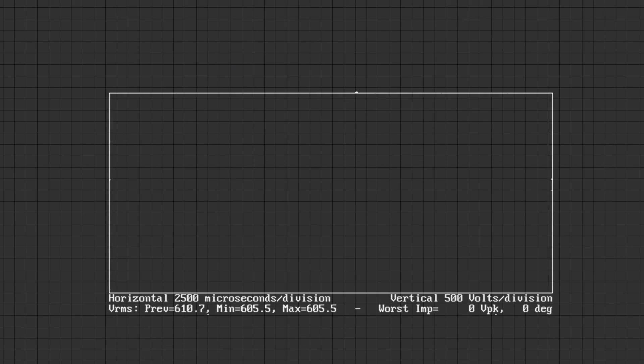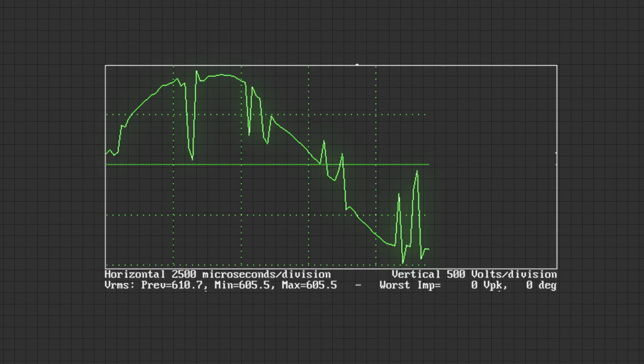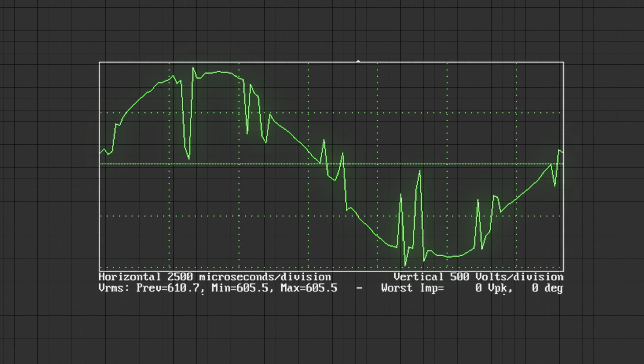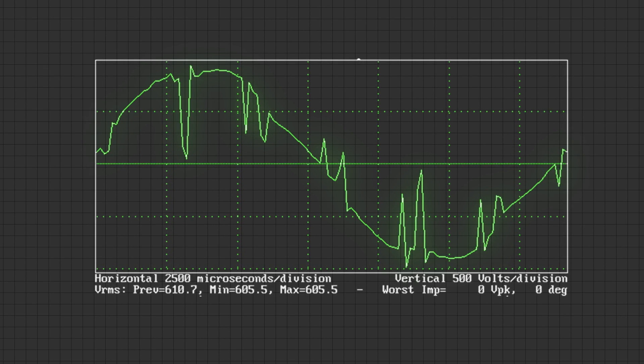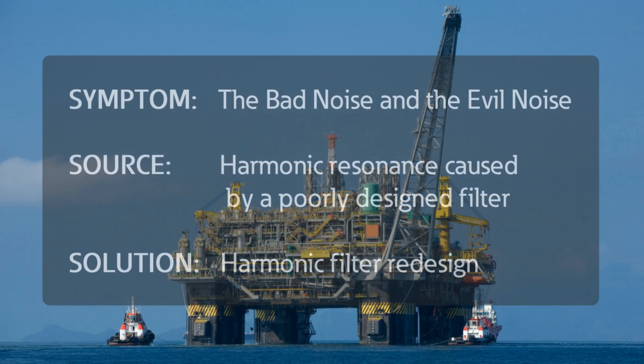Then when the current got severely distorted and the voltage got distorted even more on the generator bus, the generator's regulators actually couldn't synchronize the operation of the generator with the 480-volt bus. The generator actually slipped a pole and created the evil noise — it was like thump, thump, thump, bam. Electrical equipment really isn't supposed to make noise, especially not that kind. When it was all said and done, we helped the oil company redesign the filter and resolve the problem. We captured some great waveforms and learned a lot about harmonics. But most importantly, they came back to pick us up on the platform.